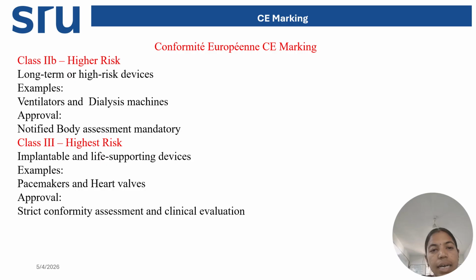Next, the second category, 2B, is the higher risk. Long-term or high-risk devices, for example ventilators and dialysis machines. These are in contact with the patient for a longer duration. So these come under the higher risk category, class 2B. These need approval from the notified body assessment, and that is mandatory before using. We should check whether it has the notified body assessment or not before selling in the European countries.